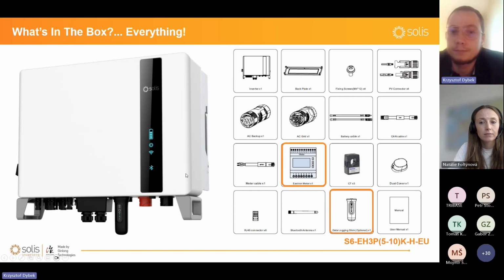Yeah, and about what is in the box, basically everything that you need to start normal operation. We do not provide batteries, obviously, for hybrid inverters, but in the box you will find a battery power cable, around 1 meter, a BMS inverter CAN cable, a Datalogger S4 with Wi-Fi communication, and a power meter with CTs, current transformers. So it is just ready for commissioning.